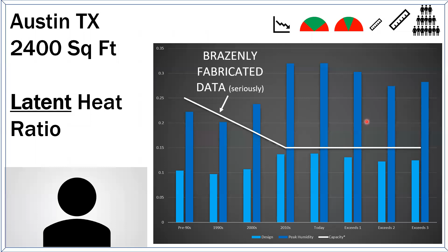So the lesson here is, I'm not saying we shouldn't make our buildings more efficient, but we are making it harder and harder to remove moisture as we improve efficiency, unless we introduce some sort of dedicated or supplementary dehumidification. If you're going to rely on runtime and you shrink your sensible load, that's going to be a problem.